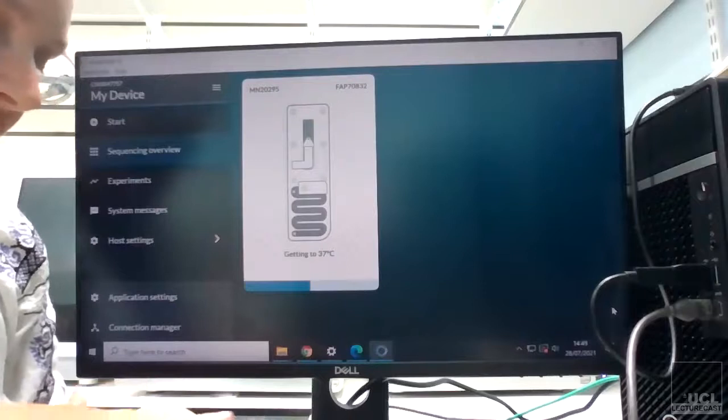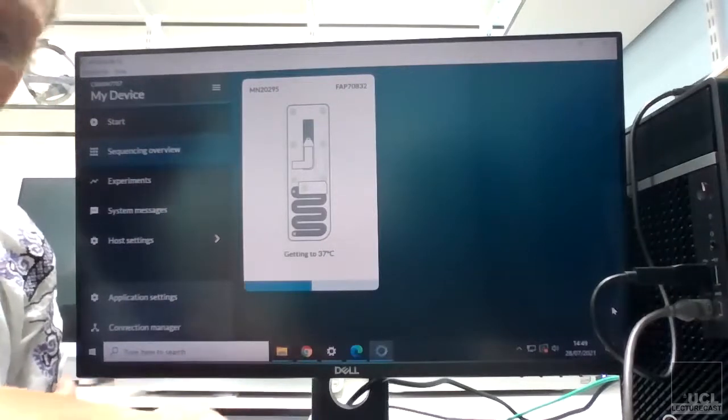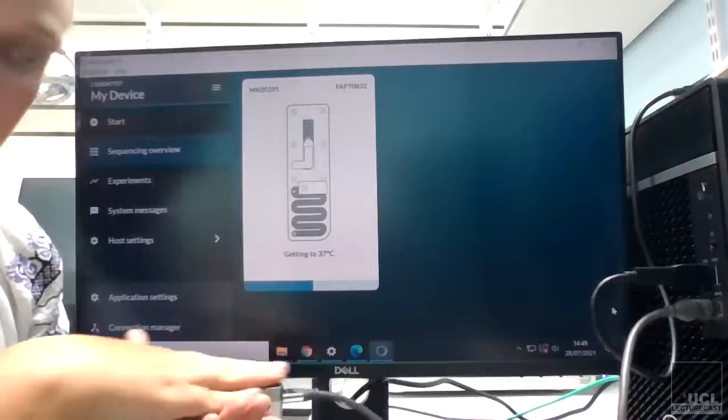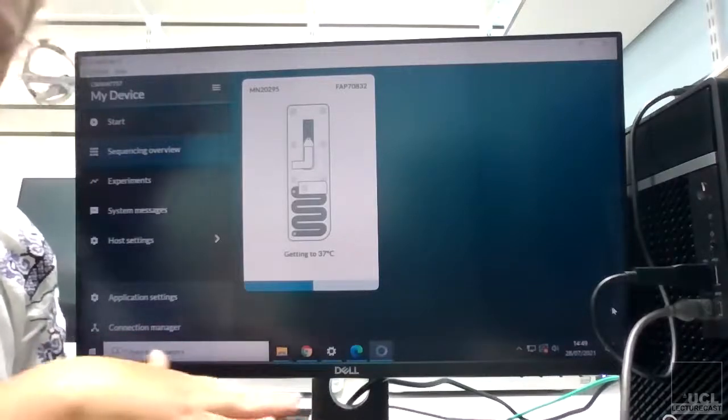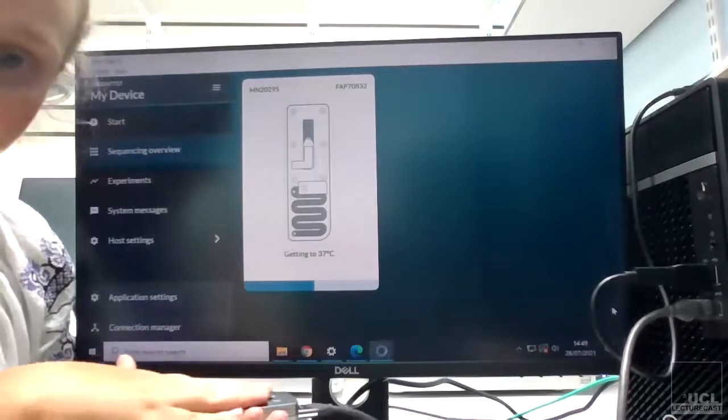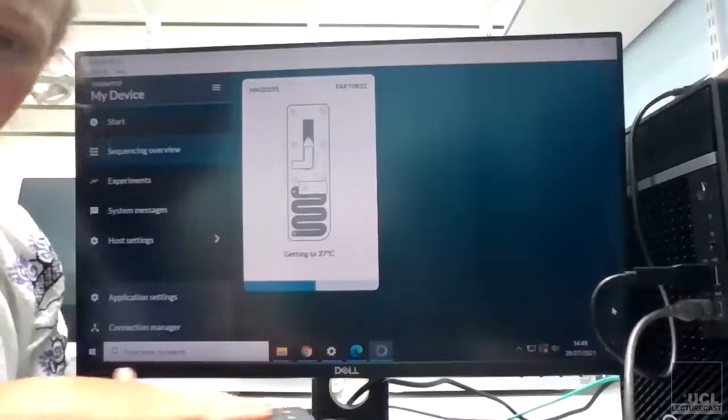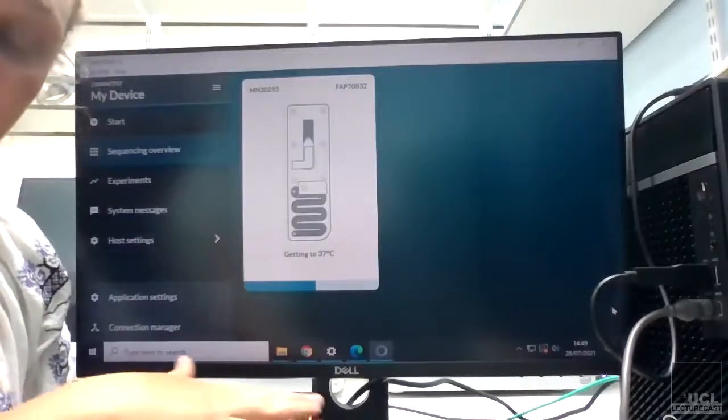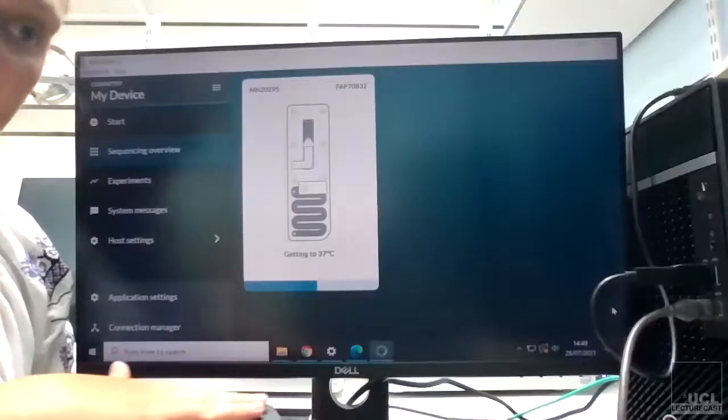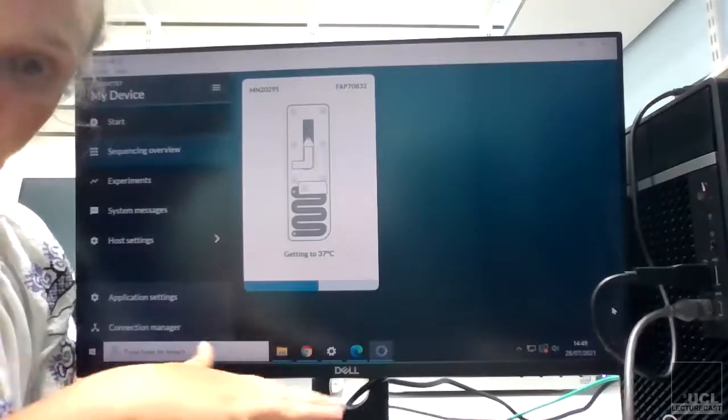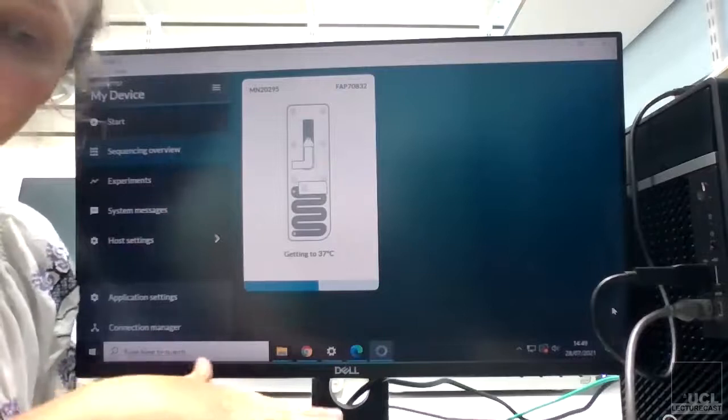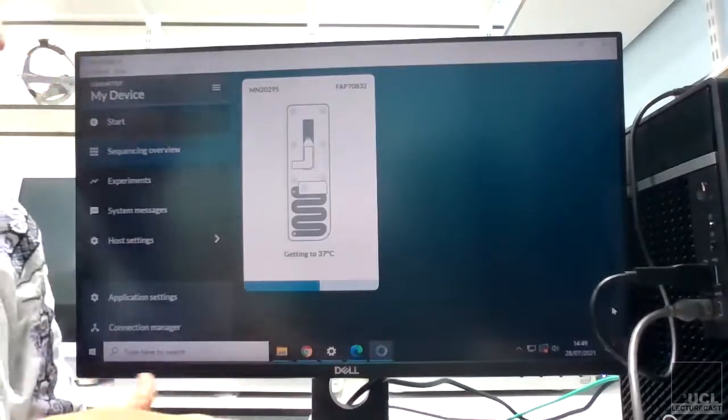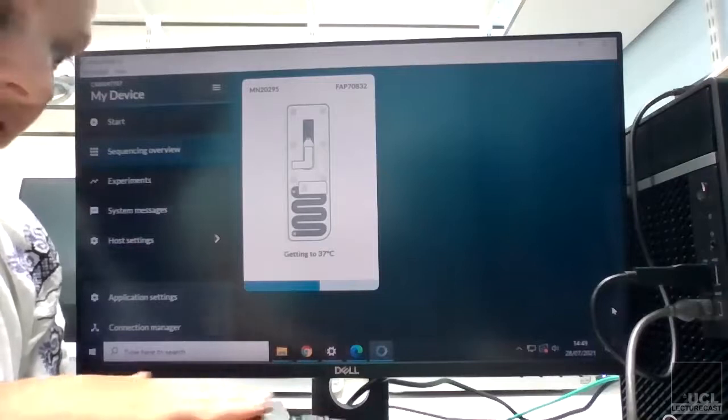So a complete flow cell for the MinION has about just over 2000 pores, but usually if it's in decent condition, it's usually somewhere between about 1500 and 1000, and anything below 800 is below the Nanopore guarantee. And so you can send it back to Nanopore and they'll replace it, which has happened a few times to us, and they were very quick about it, although maybe getting to Sudan might be different.